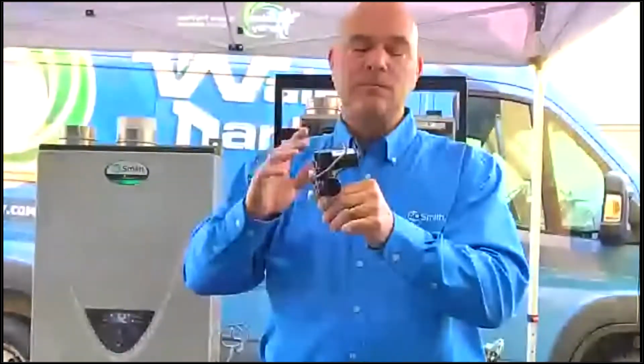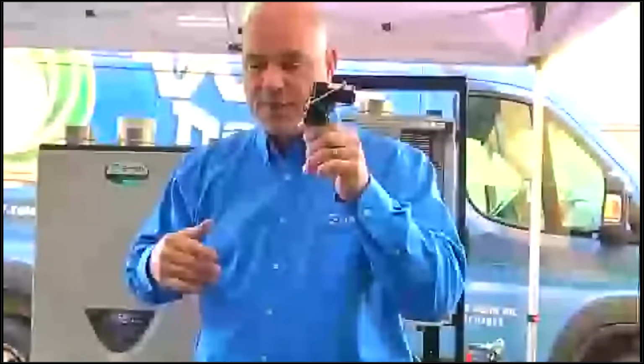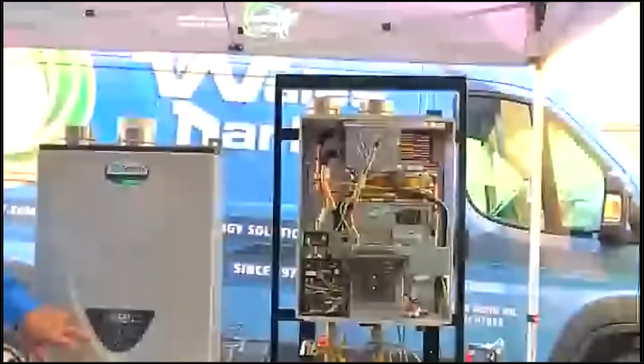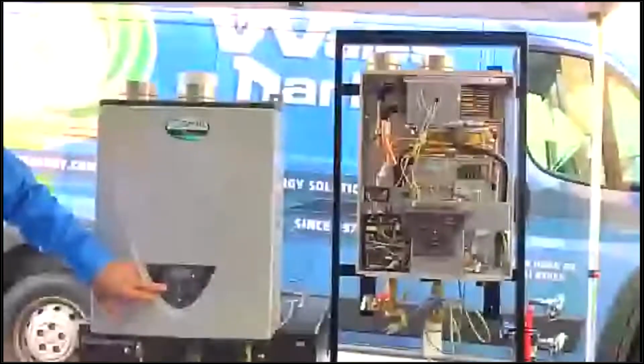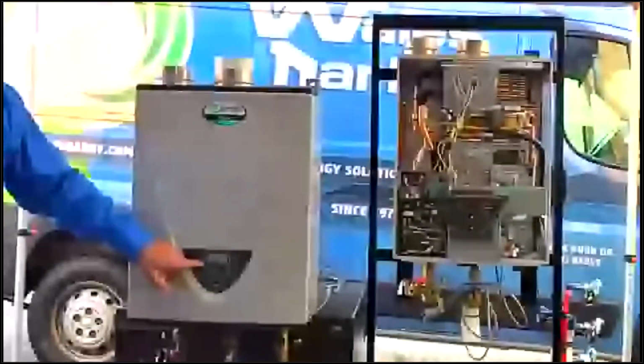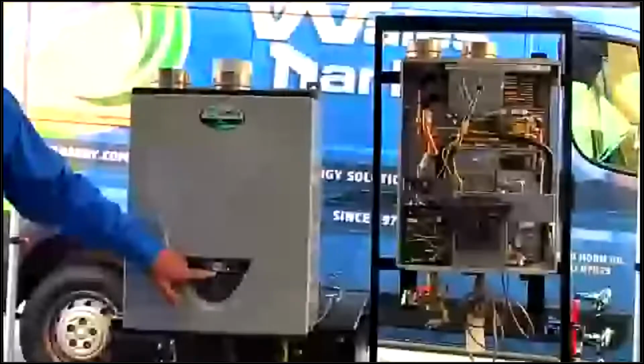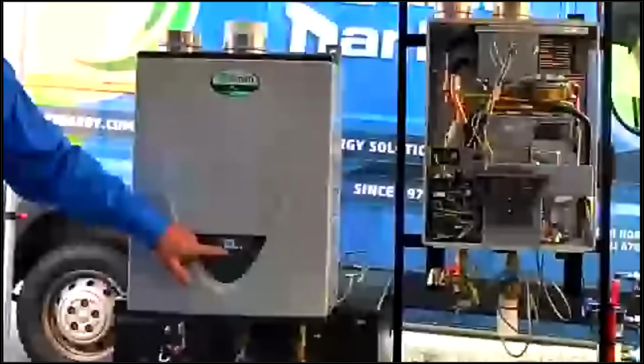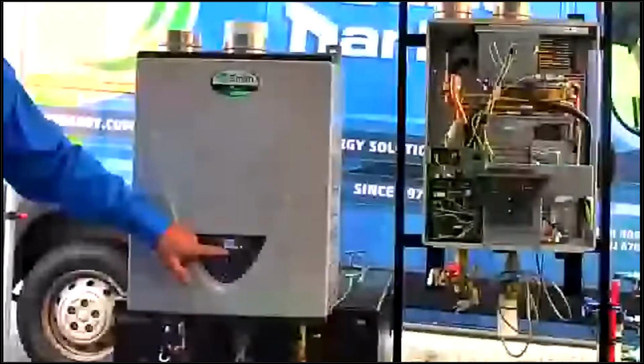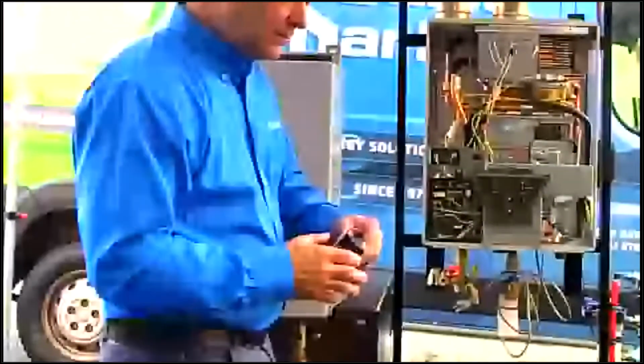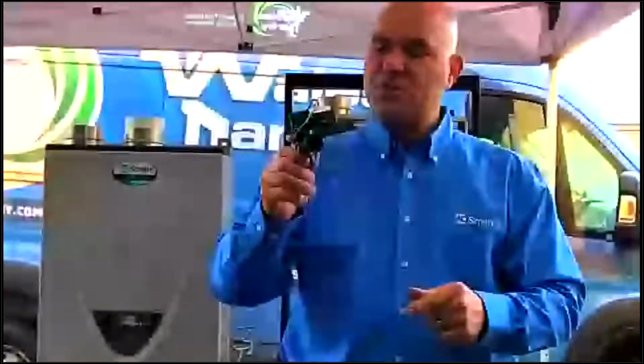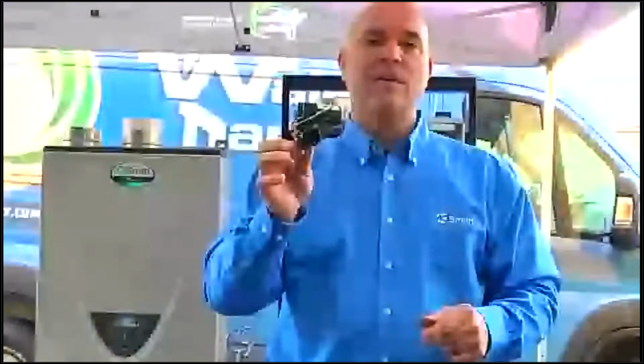How do we know this is working? Well, we can go here to the control, and if we hit the information button 3 times, that will give us the flow rate of the unit at that moment. Now, the flow switch: if this does not recognize flow, it will give you an error code.